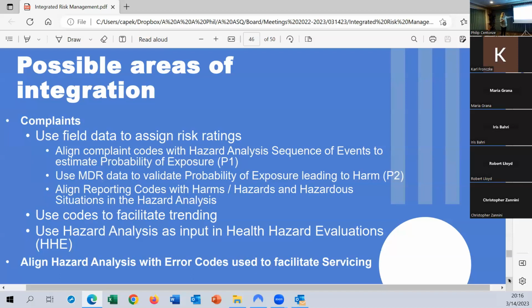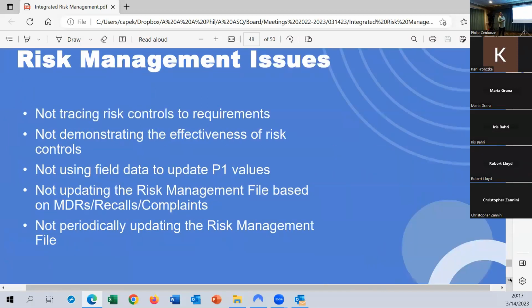So you can do a lot more than what's required and facilitate the use of data to inform your risk file. Right, so some of the biggest issues I see out there with manufacturers in risk management is they have risk controls that can't be traced to requirements or to implementation, even if you didn't have requirements. So then you can't show evidence that you verified or validated it. So risk controls ideally should be traced, should drive requirements, so that we know they're implemented in the design and we can verify and validate. Again, they don't demonstrate the effectiveness of the risk controls. I can say that anything can control a risk, but if I don't prove it, then I haven't done much.